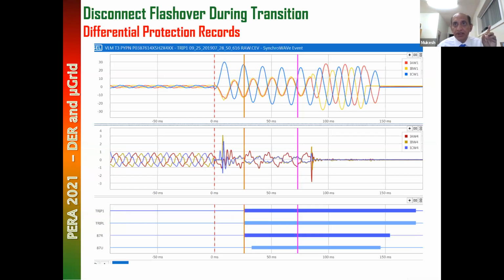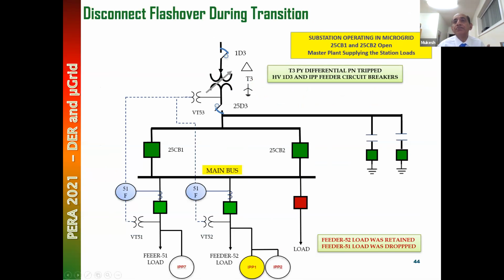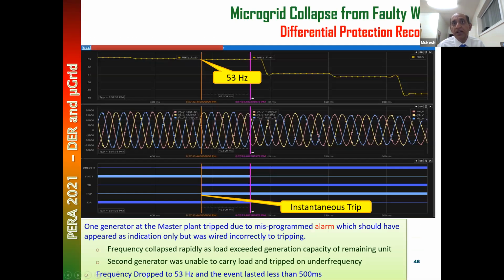Sorry, my mistake. In this case, all three generators were connected, and one of the generators tripped, and an alarm came. But this alarm wire was incorrectly connected, and it tripped one of the generators. As a result, when the generator tripped, the whole frequency started to collapse, and that's what it is showing. Because of the incorrect wire, we tripped the full master plant.